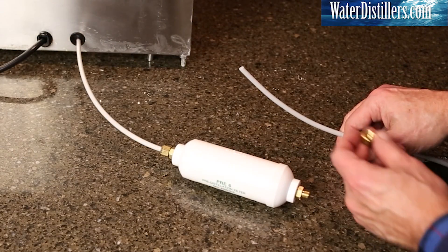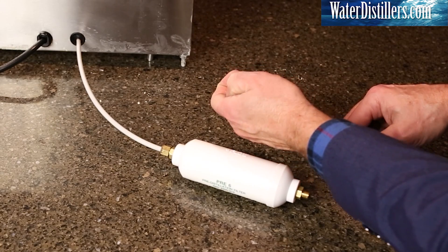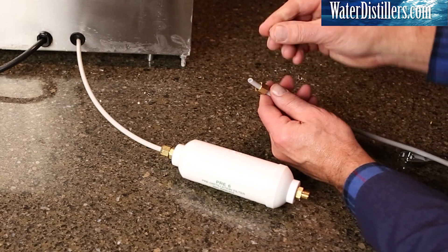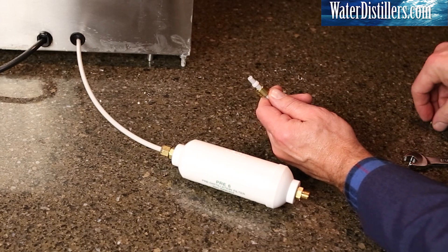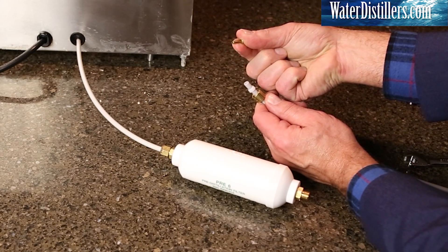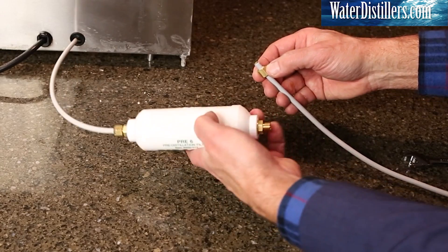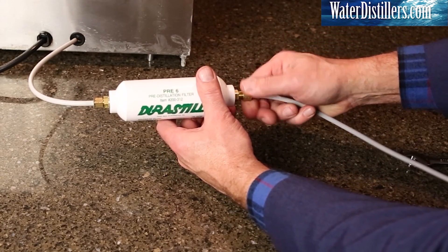For the incoming water supply line, place the nut on first with the opening pointing out. Slide on the acetal plastic sleeve — place the smaller, tapered edge towards the connection, and then the larger end toward the nut. Then place the brass insert into the tubing. Connect this now to the brass fitting on the filter, and again, you can tighten with a half inch open-end wrench.